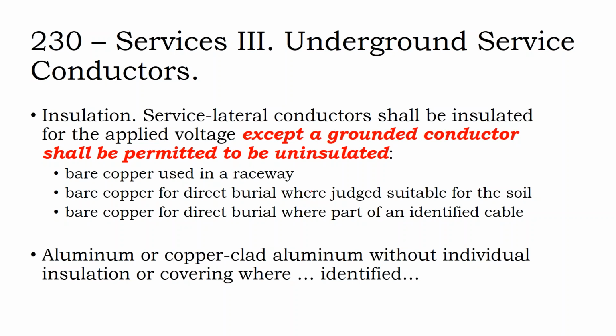Let's see. So now we have a call out that says if we're using on a service a grounded conductor, it's allowed to be uninsulated. And so in solar, when we get into our equipment ground conductor or even our grounding electrode conductor, there will be a call out that says you are allowed to use bare copper wire. You know, like yesterday we were talking about how you could have a DC grounding electrode conductor and that you're allowed to connect it to the AC side of the system. And there's a couple of different ways you can do that.